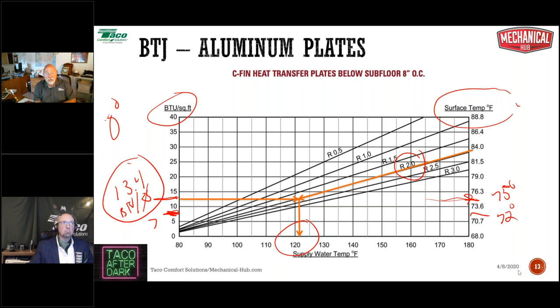And most of these European charts that we're looking at now, as John referenced, it's probably from Mr. Pex, are actually based on a 20 degrees Celsius room set point temperature. To North American folks that still use Fahrenheit, that is 68 degrees. So that's the triangle at this point in time. So 13.4 BTUs per square foot, we need a surface temperature of 75, and that's at a room set point of 68 degrees. So I think that's where he was going with that.